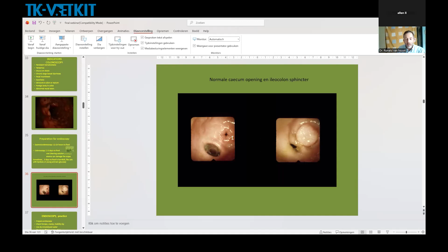Well, how does it go in practice? You start your endoscopy by preparing the endoscope, see if everything works, checking for dirt, for moisture, for lesions, for little abnormalities on the scope itself, and check also your forceps, your snares, or your instruments. Check if the mobility of the tip is good in every direction.